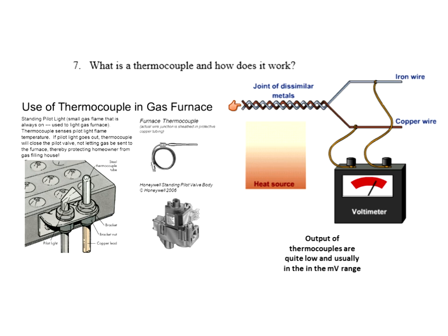If I twist two wires together of dissimilar metals, it naturally gives off a very, very tiny voltage, a voltage that's in the millivolt range, very, very tiny. Generally, if you're going to use this in a control system, you'll have to put some kind of amplifier on it to be used as feedback. But the output of a thermocouple is in the small millivolt range. I'm thinking like 1, 2, or 3 millivolts. Even that's pretty high for a thermocouple.